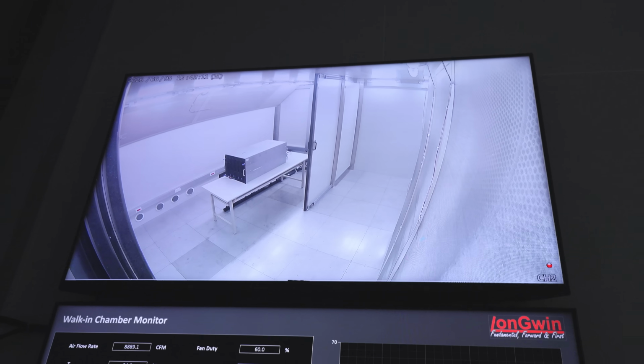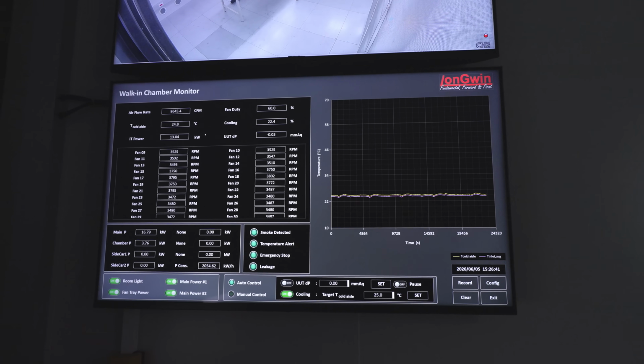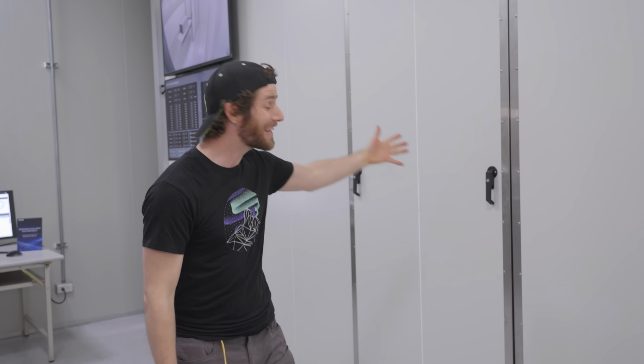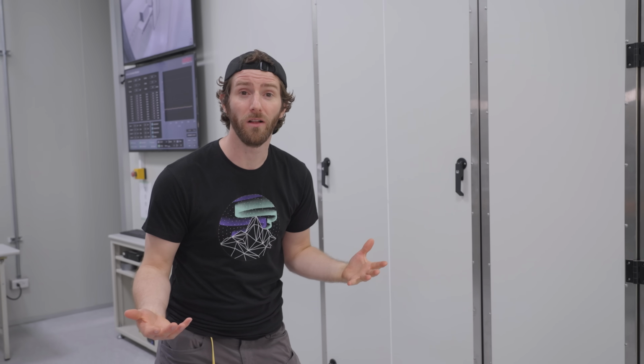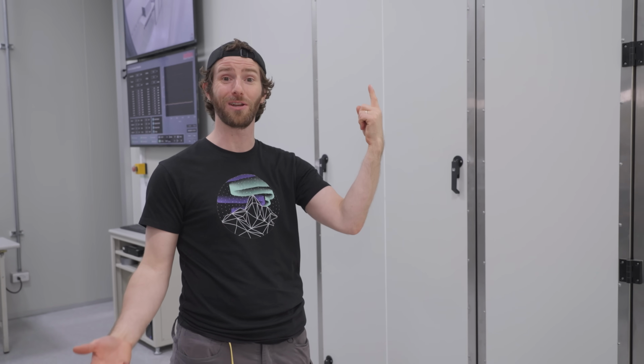In there right now is an NVIDIA HGX, and what they want to know is: okay, we can see how the fans ramp up at 25 degrees Celsius, but what if it's deployed in a data center in, say, India, and they experience some kind of challenge with their cooling? For that, they can turn this thing up as high as 45 C. How much will the fans ramp up? Will the system be stable? There's only one way to know.